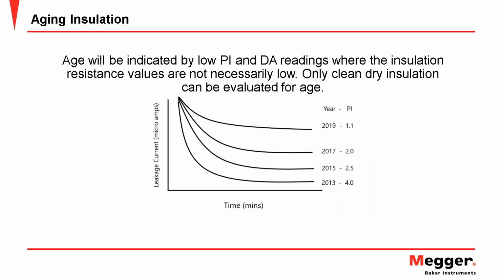So PIs and DAs are also valuable in evaluating age, but only when the winding's clean and dry. We have to get that contaminant out of the circuit so that we know that we're looking only at the insulation resistance effects on that current changing over time. And this graphic illustrates that nicely: over the years, we see a slowly degrading change in current. Okay, a PI is evaluating an early reading at about 1 minute to the reading at 10 minutes. The DA does from 30 seconds to a minute or 30 seconds to 3 minutes, and we evaluate the change when it occurs earlier on, more quickly, if you will, for smaller motors typically.